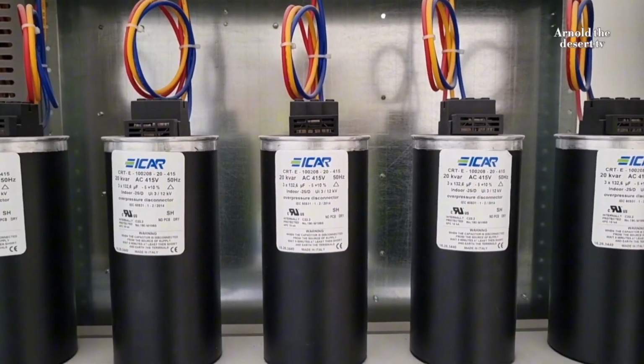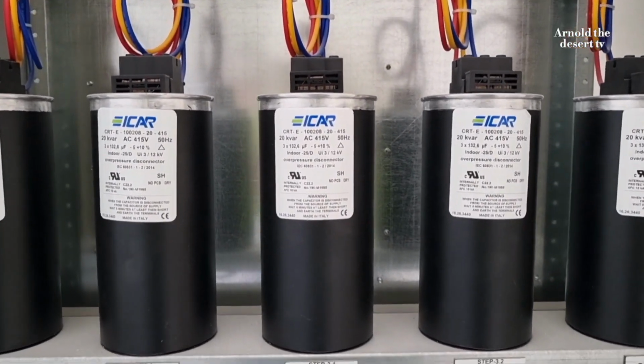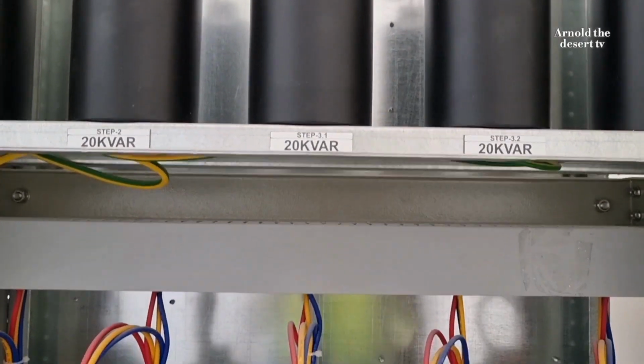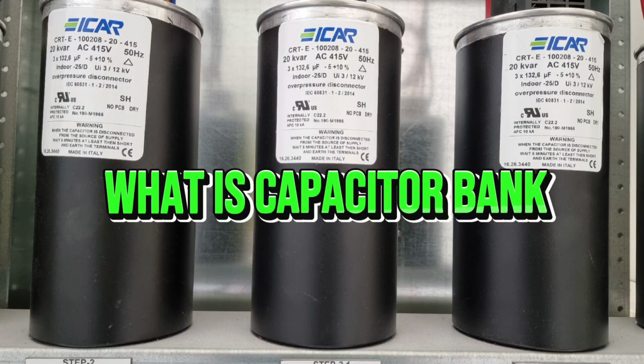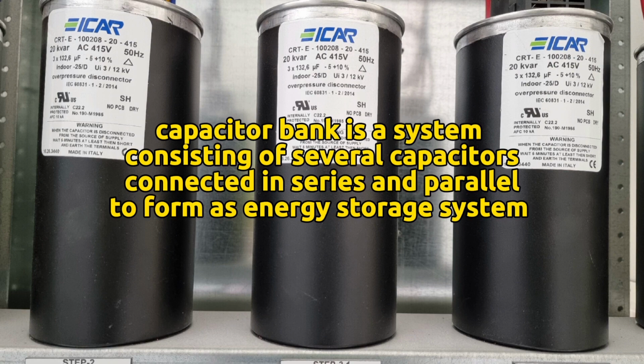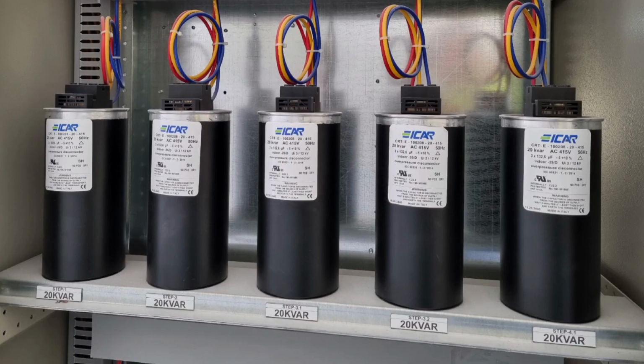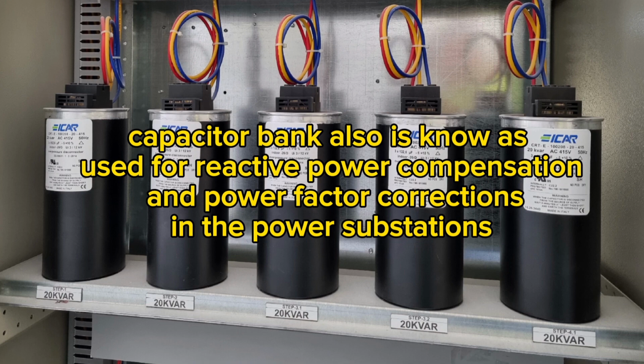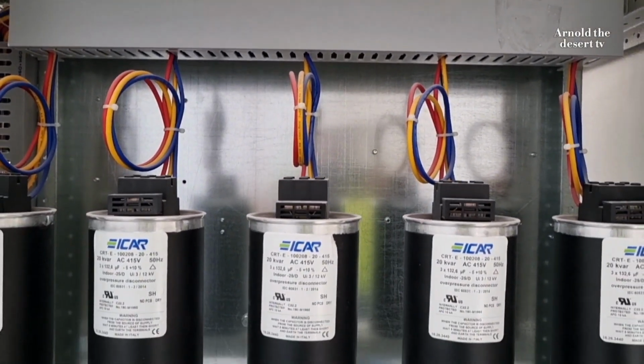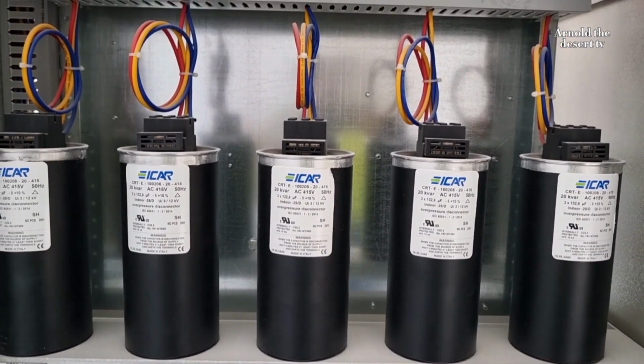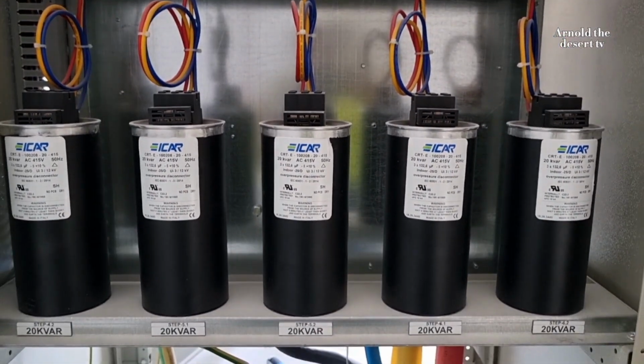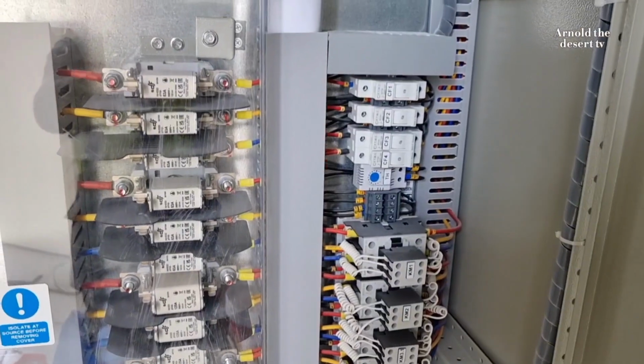And now, introducing the capacitor bank with a power of 20 kVAr each. What is a capacitor bank? A capacitor bank is a system consisting of several capacitors connected in series and parallel to form an energy storage system. A capacitor bank is also known as being used for reactive power compensation and power factor correction in power substations. A 1000 kVA power transformer uses 10 units of capacitor bank with a power of 20 kVAr each.